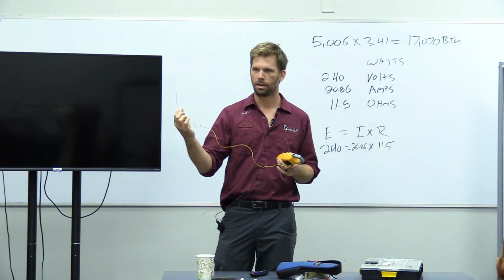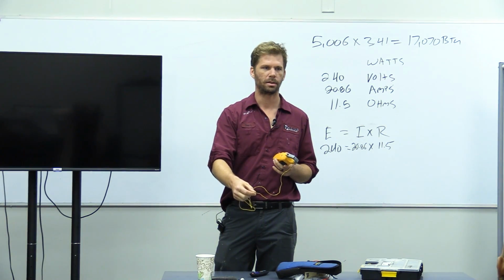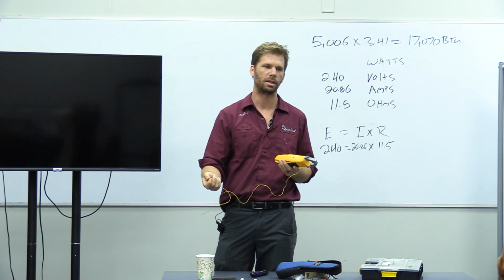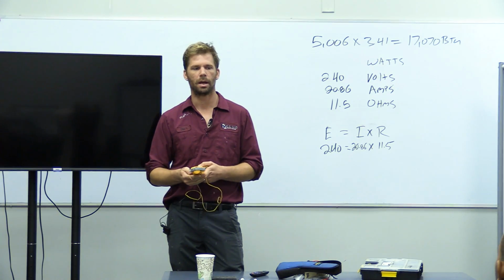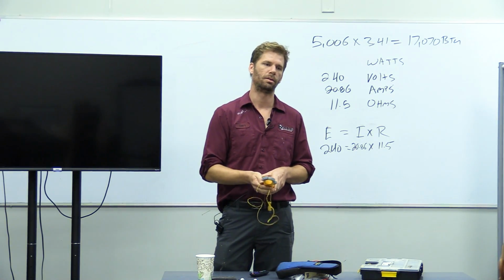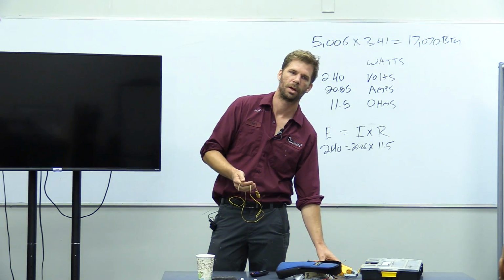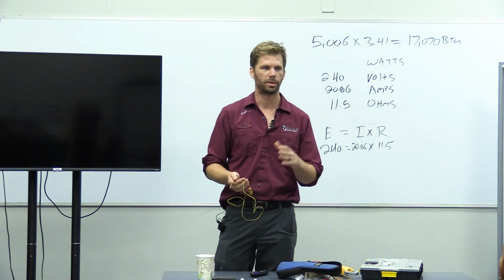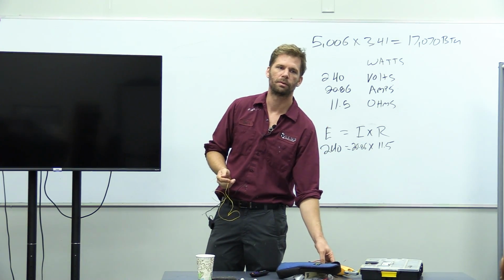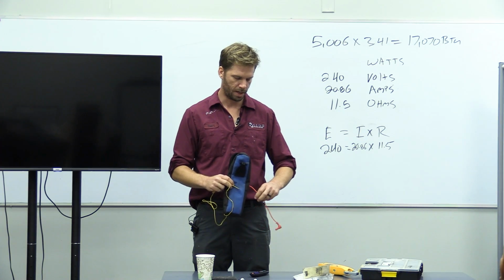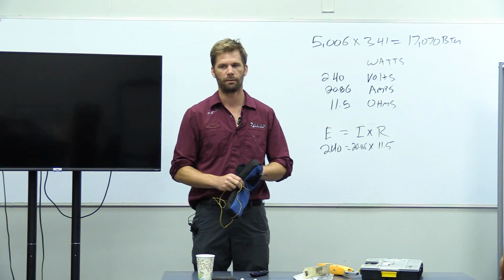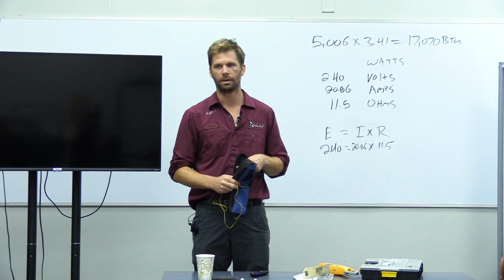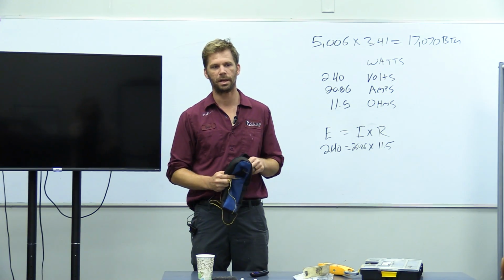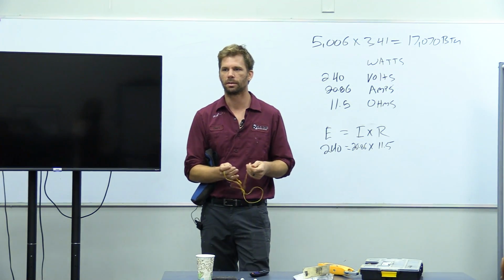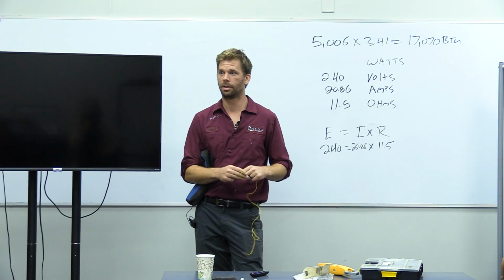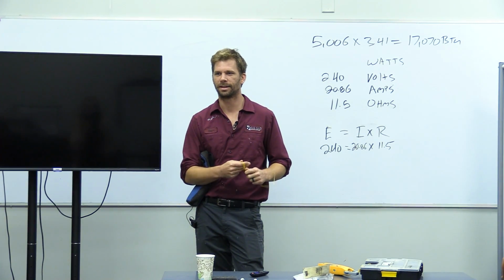Then you take your other probe and stick it straight into a jet somewhere when the pool heater is running. If the pool heater is running, you should typically see a 3 degree difference. Depending on the weather outside, it could be a 3 to 7 degree difference. If you have great weather outside and it's picking up a lot of heat and your pool's colder, you're going to see a more extreme temperature split. But if you're getting a 3 degree difference, you can have full confidence that your heater is doing its job. Even if it looks low on refrigerant because it's a colder day or whatever, you can have confidence to tell the customer that. And a lot of customers are like, 3 degrees, are you kidding me? That's all it'll do? Yeah, that's the design. That's all it'll do.